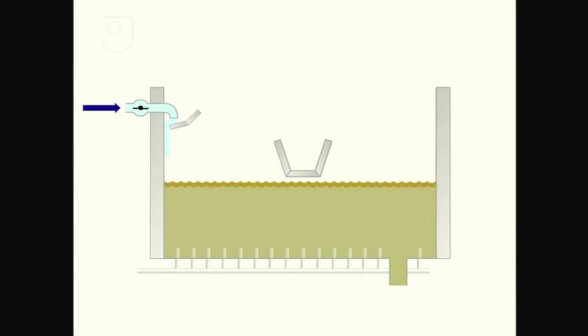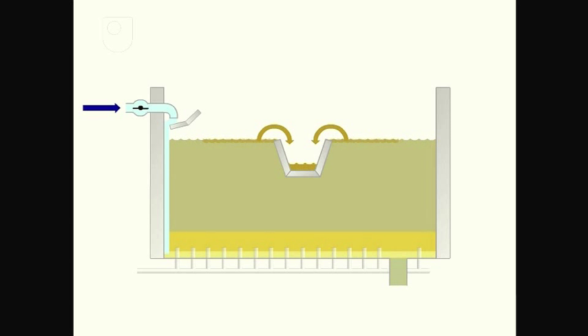Clean water is pumped in and this fluidises the bed of sand so that the dirt is now in suspension above the sand. The water flow is then increased so that the scum and the dirty water cascade into the outflow trough.